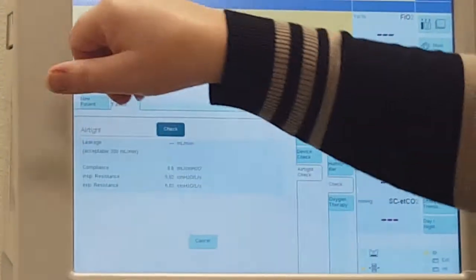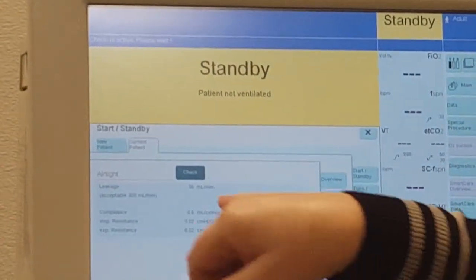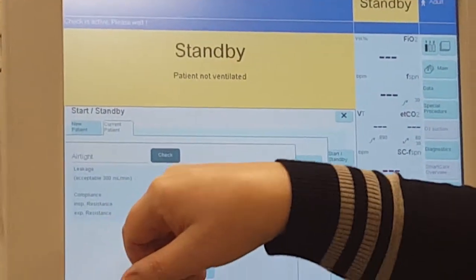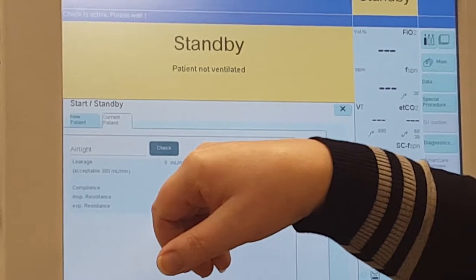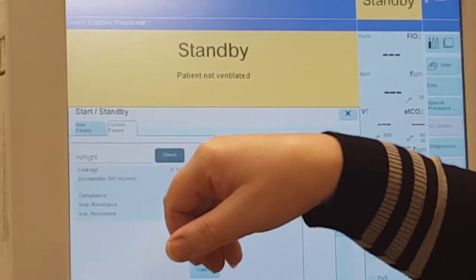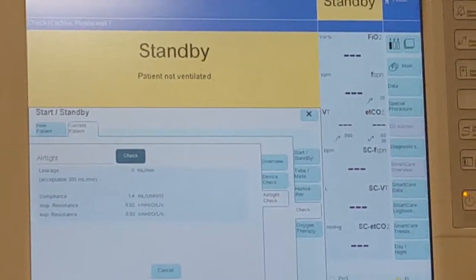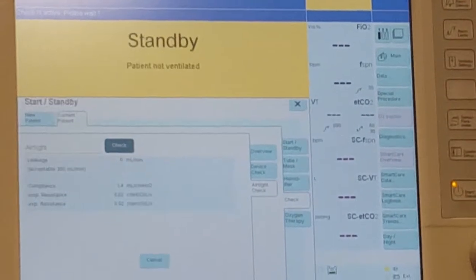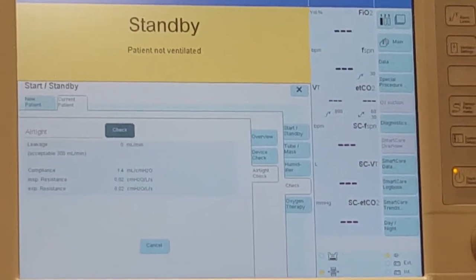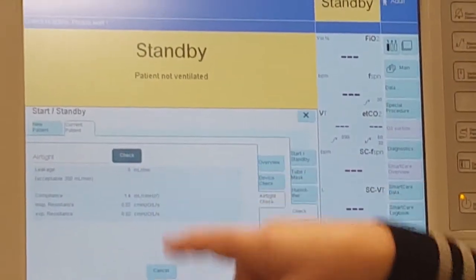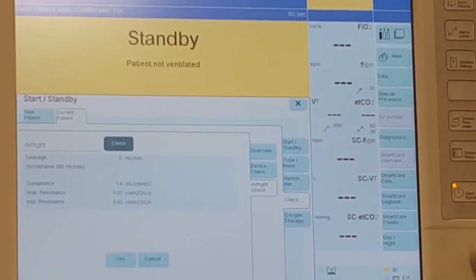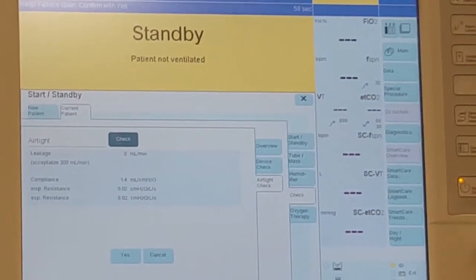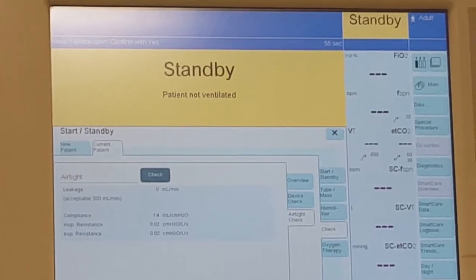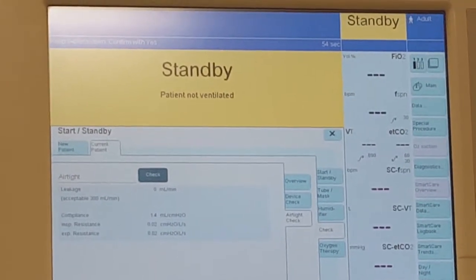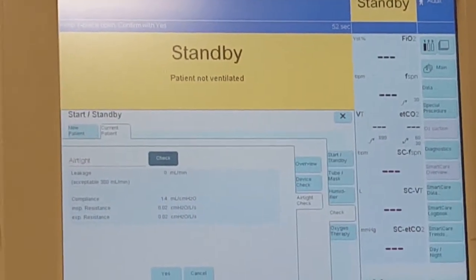Now you'll see maybe some numbers come up in here. It's going to say check is active, please wait. It's looking to see that these numbers don't go above 300. If they go above 300, that means the leak is too large. So it's going to do a whole bunch of stuff, and as long as you see it end up back at 0, you're good. You'll see if it's not at 0 because it'll run and read some really high numbers, and then that tells you you have a leak. So you really have to watch what this one is doing.